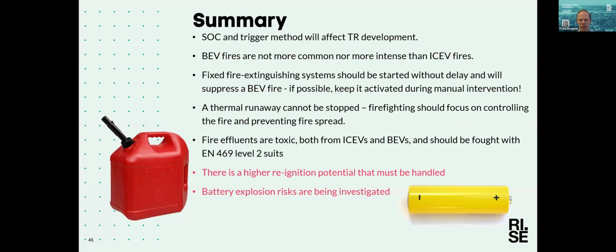Fixed firefighting systems could be started. It should be started without delay and will suppress the BEV fire, the flames that is, but once again you will not extinguish or stop the thermal runaway with the system. So therefore, it's important to keep it activated during a manual intervention.